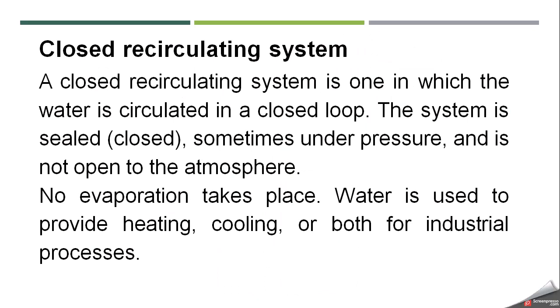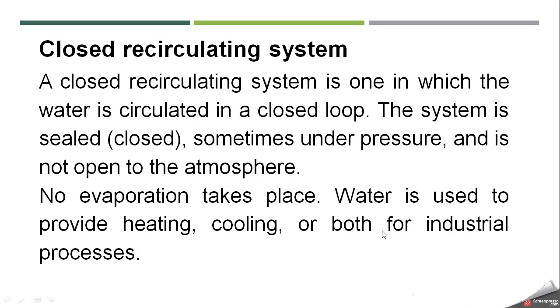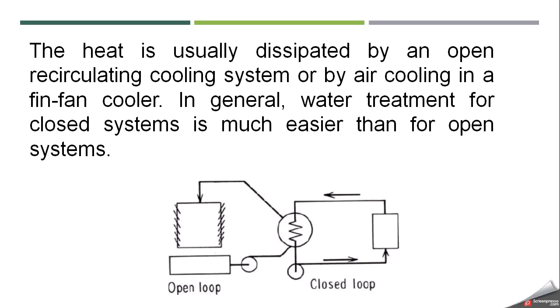A closed recirculating system is one in which water is circulated in a closed loop and the system is sealed — no leakage and no replacement of water takes place. Sometimes the system is under pressure and is not open to the atmosphere. No evaporation takes place and the water is used to provide heating, cooling, or both for industrial processes. The heat taken by the closed system is usually dissipated by an open recirculating cooling system or by air cooling in a fin fan cooler.